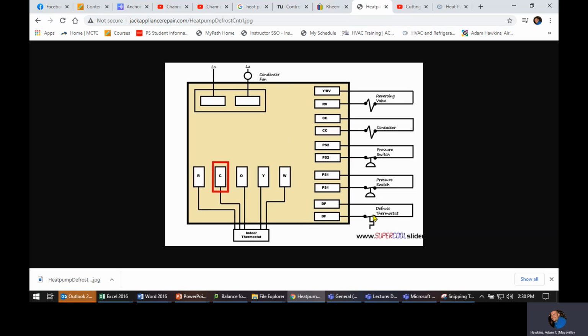Now, just because the thermostat closes and says that we're freezing doesn't make everything go into defrost, because think about it. If that unit's sitting there running and it's 20 degrees outside, obviously that stat is going to be below freezing. So if it called for it every time the coil got below freezing, it would just be in a constant state of defrost. So what it does is that board actually has a timer on it that you set to a certain time, 30, 60, 90 minutes usually on a lot of them. Every 30, 60, or 90 minutes, that board will check this switch. So it's got a clock in it. That clock starts to count, that motor starts to turn, and after 30, 60, or 90 minutes, that board checks this stat, and it sees if this stat is in a freezing state or not.